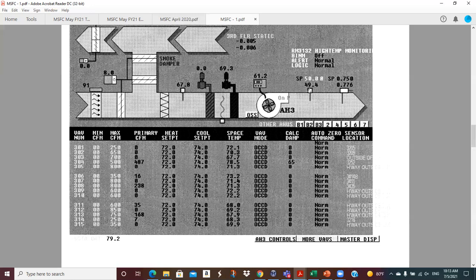And this, say, is the supply temperature, 49.4 degrees with a set point of 50. That just blows me away. That's extremely cold. Unless maybe that's a design. Maybe these are cold air distribution systems. I don't know, but that's awfully cold air. If the insulation's not really good, if moist air gets to the outside of this duct, it's going to condense and that water is going to drip on something.